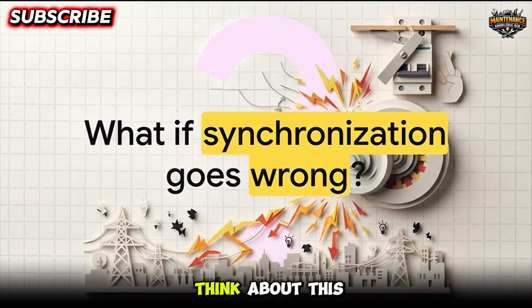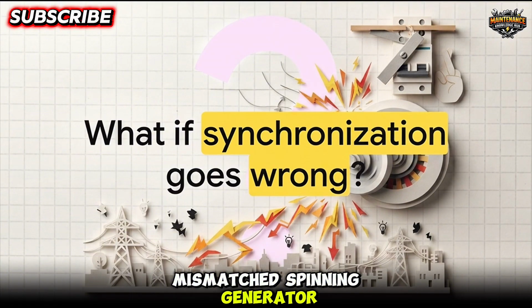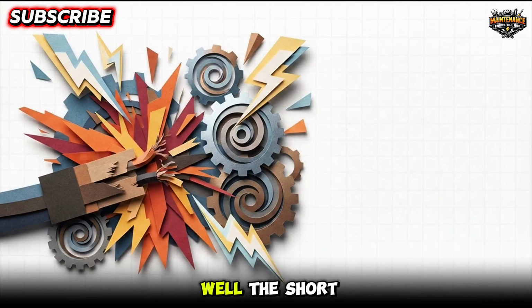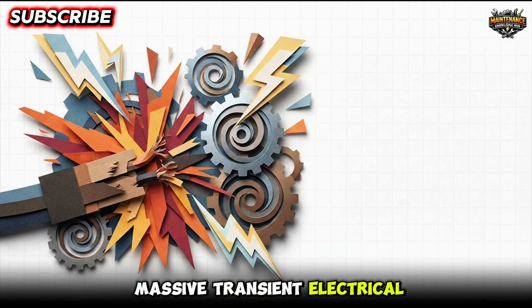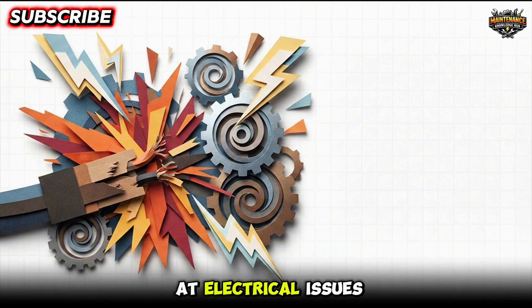So I really want you to think about this. What actually happens if synchronization goes wrong? What if we just sort of cross our fingers, blindly close the breaker, and connect a mismatched spinning generator right to a live grid? Well, the short answer, complete devastation. If the grid and the generator are significantly mismatched, the second you close that breaker, you produce this massive transient electrical current. But it doesn't even stop at electrical issues.